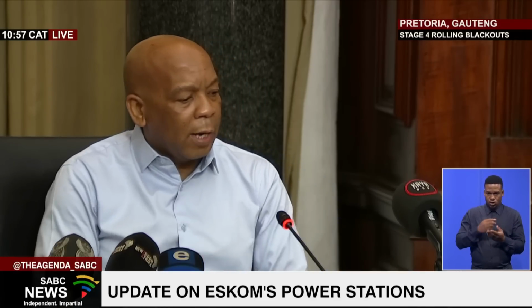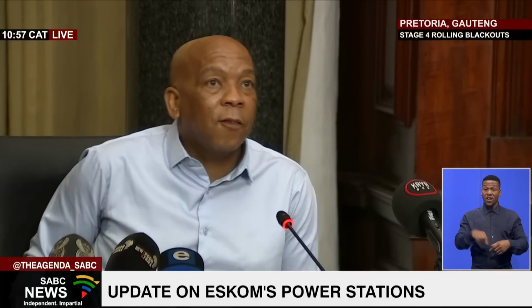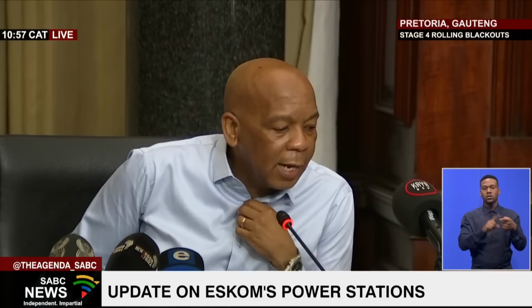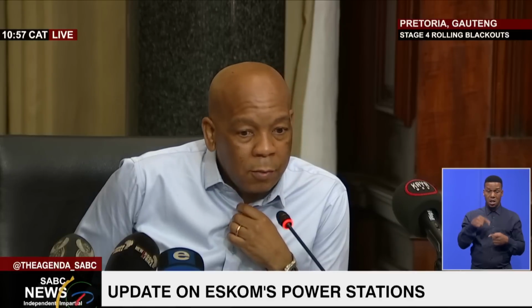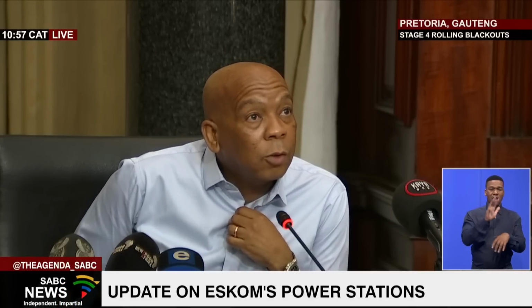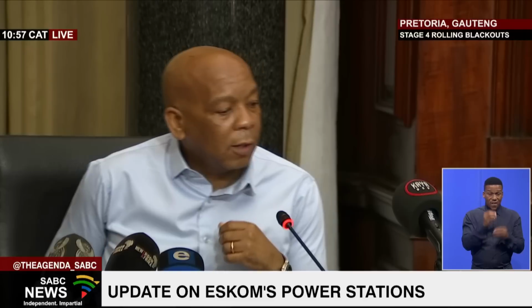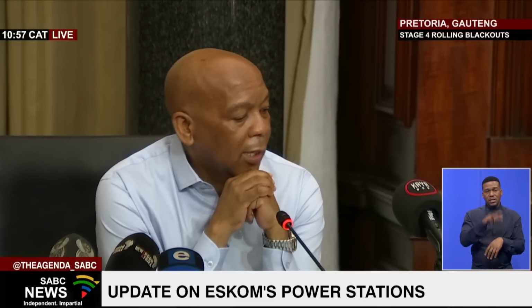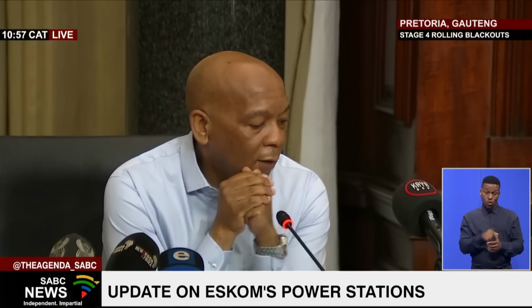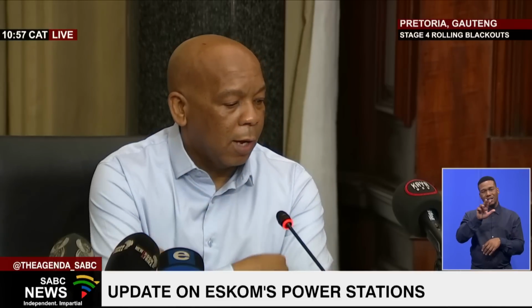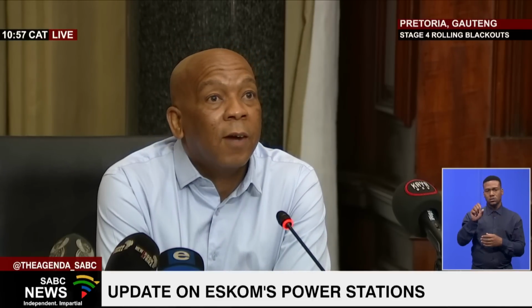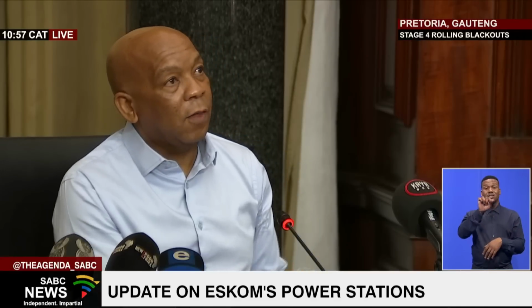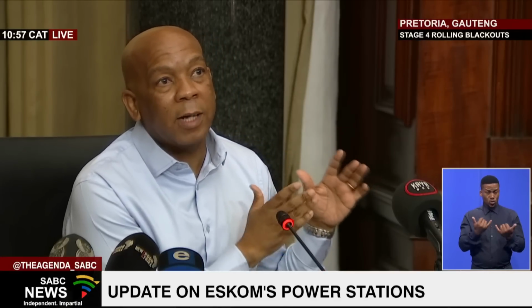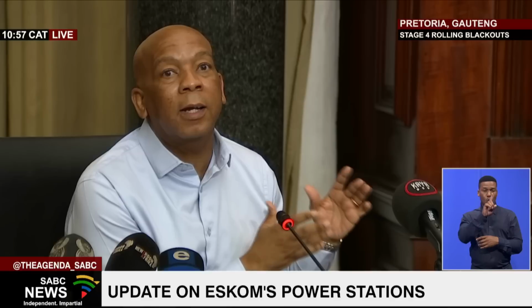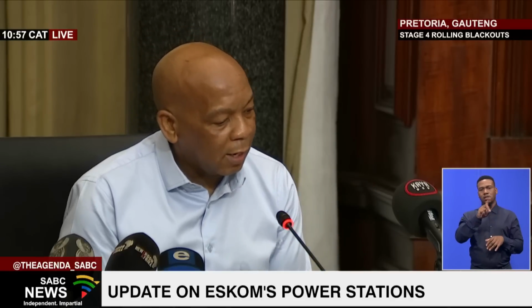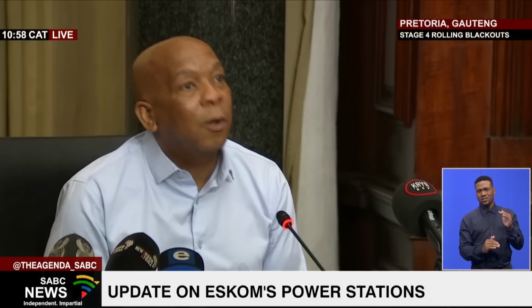I'm starting with the first one, Kendal. Kendal's first unit was commissioned in 1988, and the last unit was commissioned in 1992. The installed capacity is 4,116 megawatts, and the energy availability factor, as I speak to you now, is sitting at 46.75%. So of the 4,116 megawatts installed at Kendal, they are giving us less than 2,000 megawatts. Why is that the case?